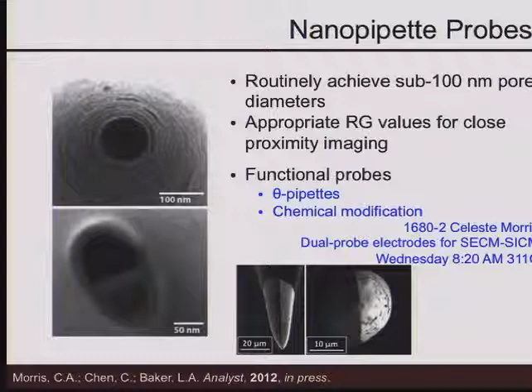So the other thing about this technique that we do, or that's different from typical SECM experiments, is that we use a modulated feedback. Bard developed this for SECM, but the SICM community picked it up. So what we do is we actually vibrate the tip in the Z direction in space. What that does is when the tip gets very close to the surface, this modulation produces a modulated resistance between the tip and the surface, and we can use that to control the feedback loop then.